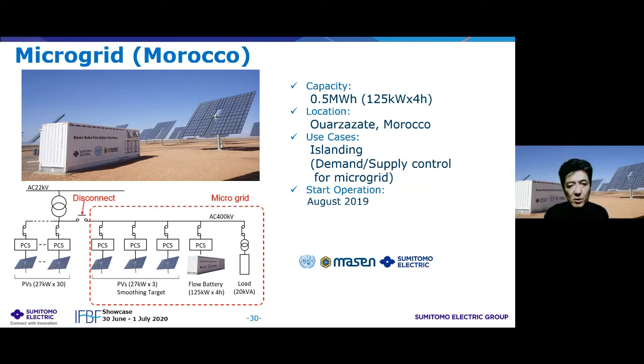This system is connected to PV, and this is an example of microgrid operation. In this microgrid, the flow battery takes the role of voltage source of the microgrid. In the graph, the green line shows the PV output, and the red line shows the flow battery output. The connected load is 20 kilowatts, and the blue line is the total output of PV and the battery. The blue line can be maintained at 20 kilowatts, the same as the load, by adjusting the output of the flow battery according to the output of the PVs.